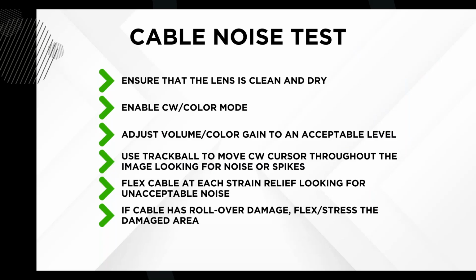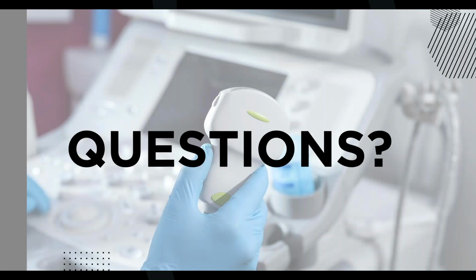A typical PM per ultrasound system takes me about an hour if there's like 8 or 9 probes for the system. Obviously, it's quicker if there's just one, and it depends on whether or not it's a portable system or a larger system. These are quick and easy to clean out and make sure that the fans and everything are clean. The other systems are not. One of the things I do, I think that's everything under quality assurance for tests. Any questions on quality assurance for transducers?